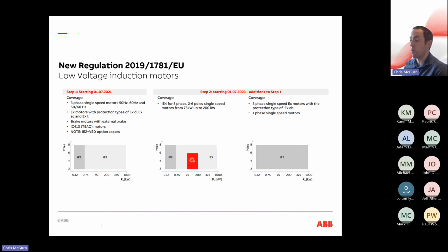IE4 is a requirement. So if you're buying a new system now, it's an EU requirement that if the motor is between 75 kilowatt and 200 kilowatt, and between 2-pole and 6-pole, and generally 2-pole and 6-pole is a typical speed for an electric motor, they have to have an efficiency level of IE4. Outside that band, between 0.75 kilowatt to 1,000 kilowatt, you're looking at IE3 level efficiency, and below 0.75 you're looking at IE2. So this is a regulatory requirement for all motors that are being supplied in any industry in the EU.